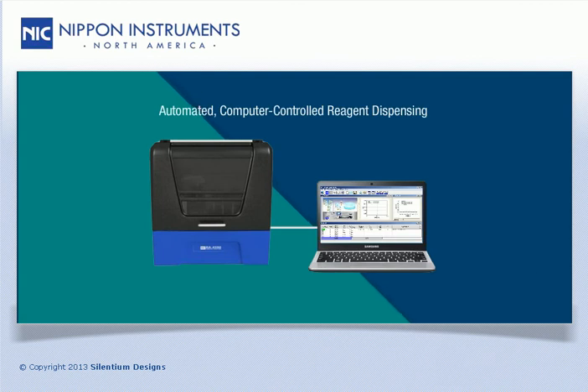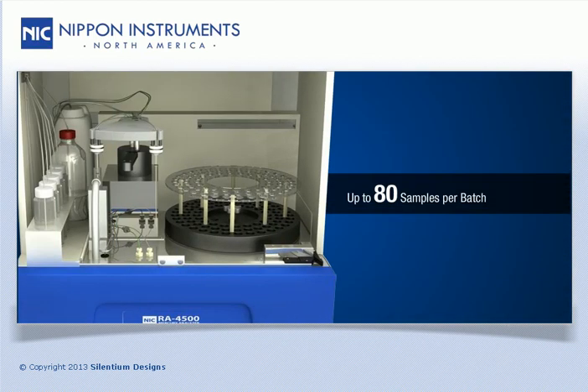The RA4500 has the capacity to dispense up to 6 different digestion reagents and it can analyze up to 80 samples at a time.